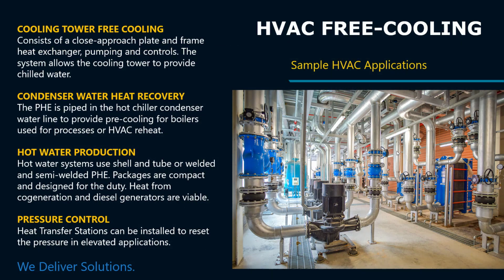We built a number of free cooling systems for HVAC duty. One is the cooling tower free cooling approach, where the system allows the cooling tower itself to provide the chill water by placing a plate and frame heat exchanger and some pumps and some controls in between.